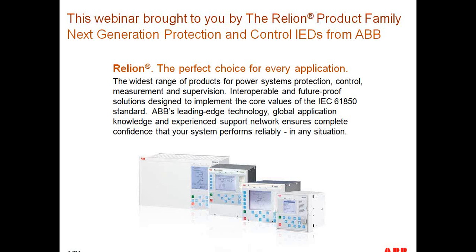However, you cannot use Goose messages to do a line differential scheme. In a line differential scheme, you are exchanging samples of data from one terminal to the other. Each relay at each terminal evaluates the local samples versus the remote received samples, takes a delta or subtraction between those two quantities, and determines the current coming into the line versus the current coming out of the line. You cannot do that with Goose messages. However, sending the bits for unblocking or permissive pilot schemes is something that you can do.